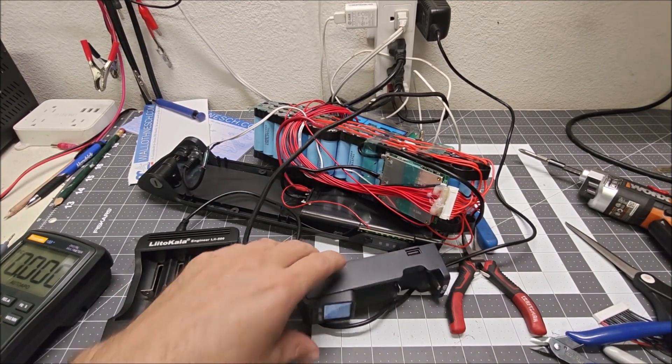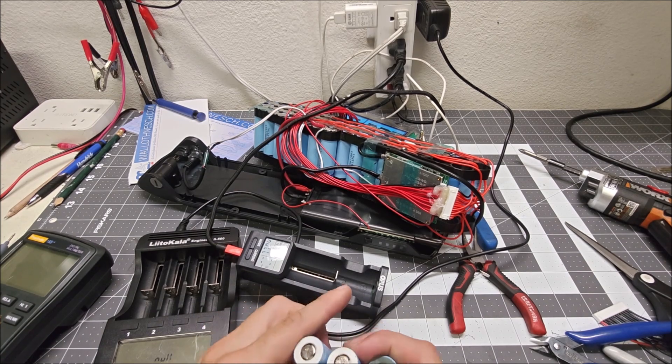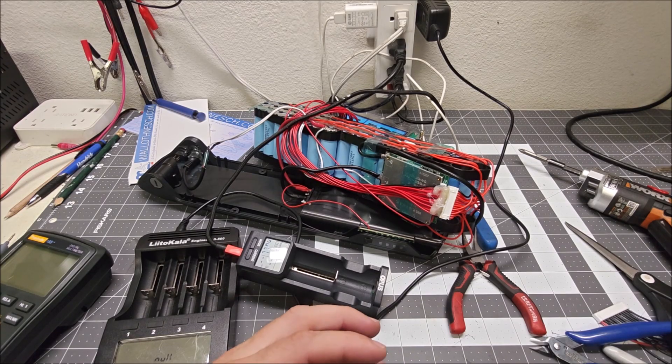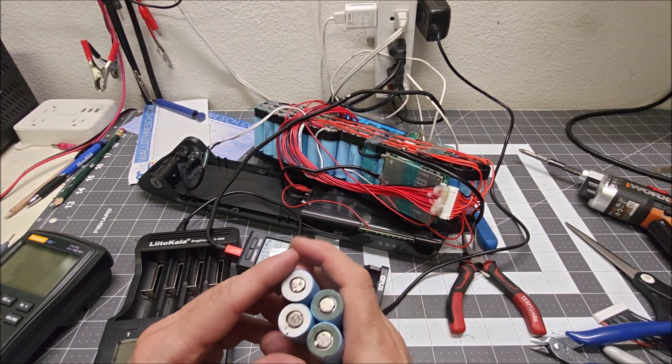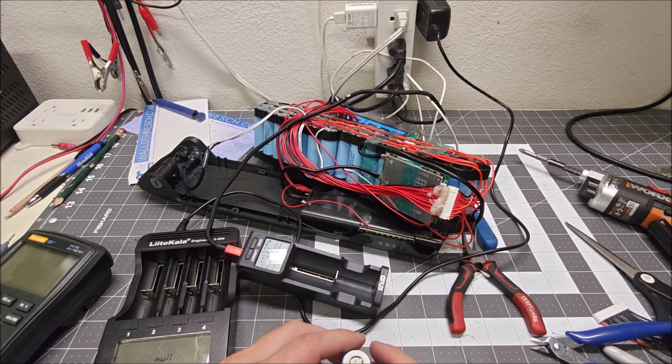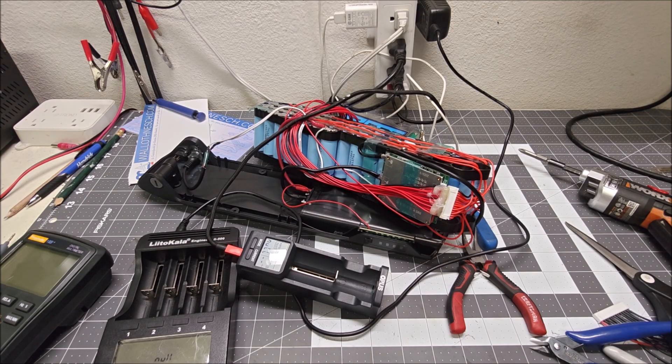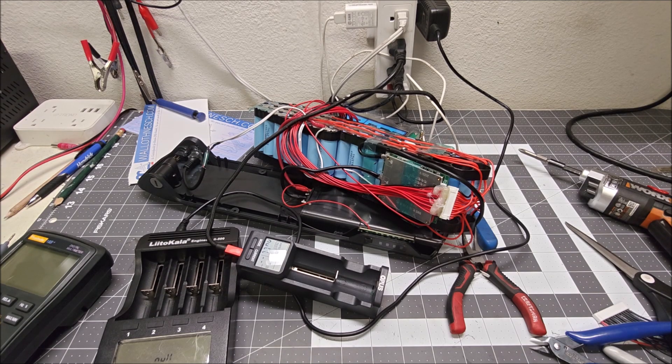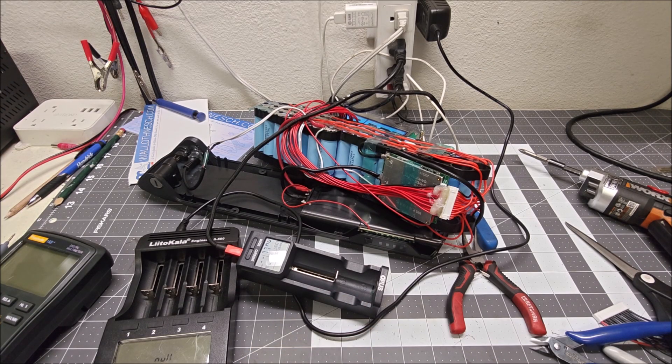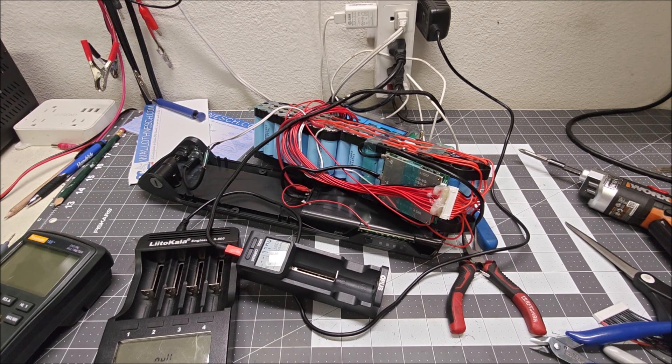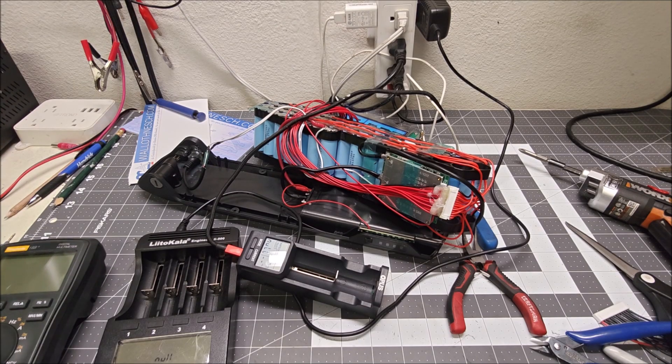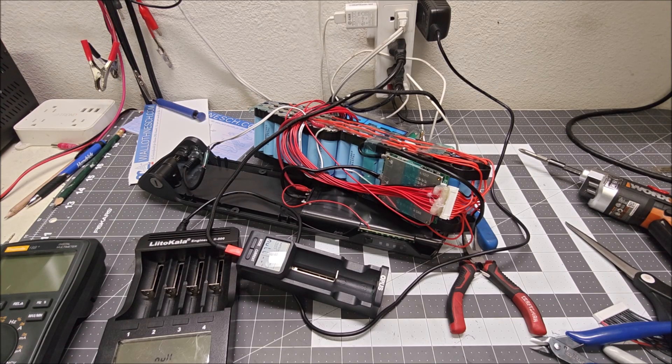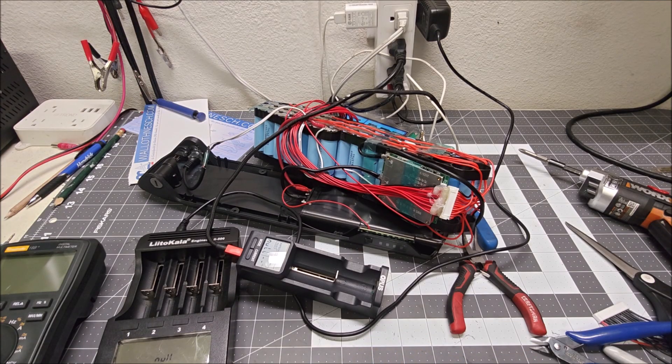I ran them through my two testers here, and I'll be honest, I can't seem to get consistent readings on the internal resistance of these cells. Sometimes they read high, sometimes they read low. I'm not super happy with the readings I'm getting. I am tempted to just replace all four. I think that's what I'm going to do just for speed of getting the battery back up and operational. I'm going to grab four fresh ones, four that have been sitting on the shelf for a year and still have over 4 volts.